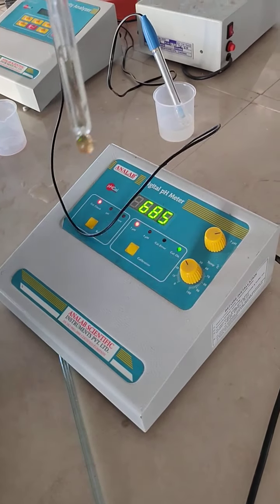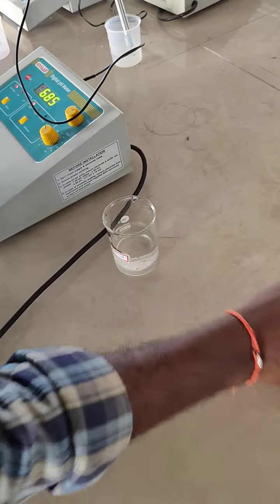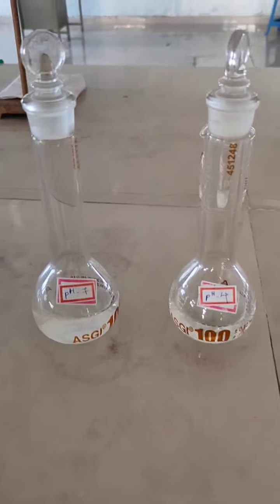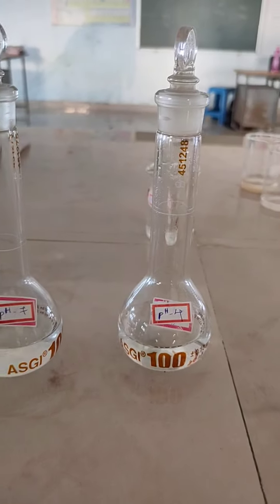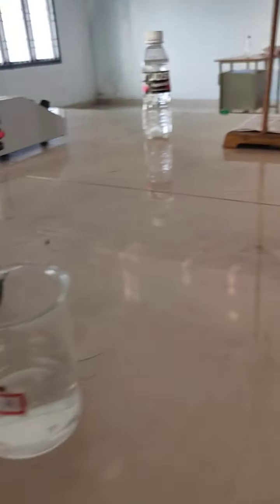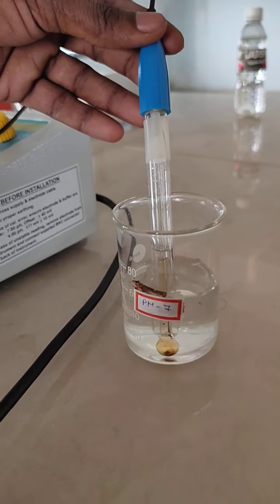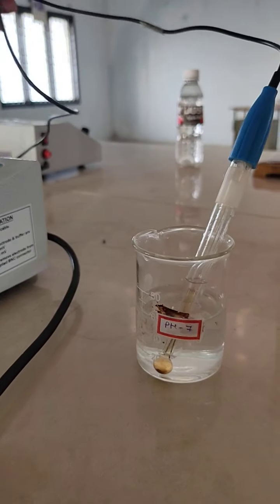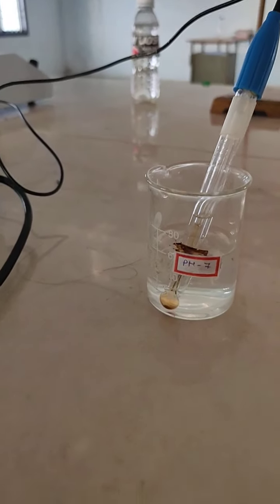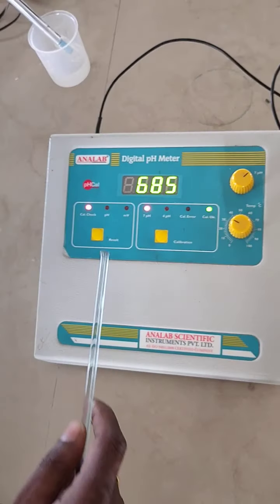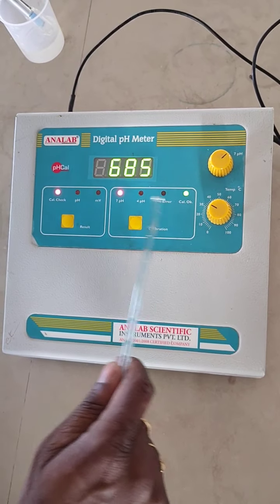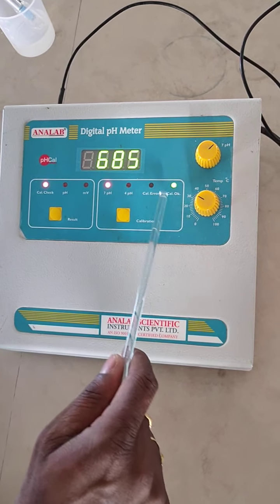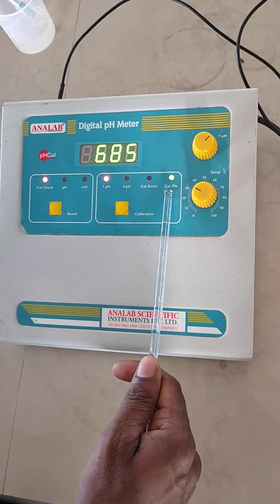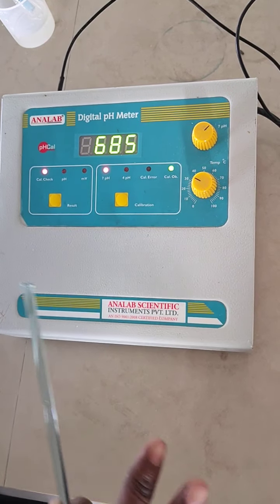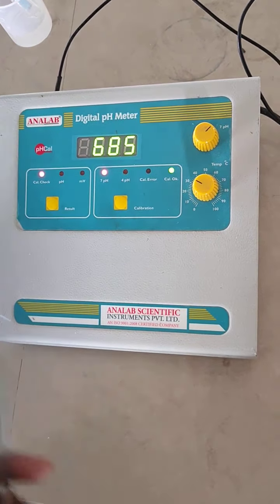So for that, first we have prepared two solutions, a pH 7 solution and a pH 4 solution. These two are buffer solutions. We have taken the pH 7 solution in the beaker and we are dipping the glass electrode in pH 7. Okay, then observe the reading on the meter. If it shows the green light on calibration okay, then the 7 calibration part is over. Okay, then wait for 2 to 3 minutes.